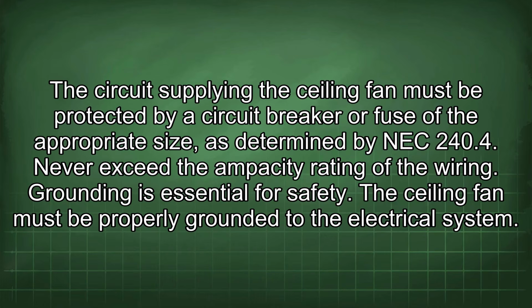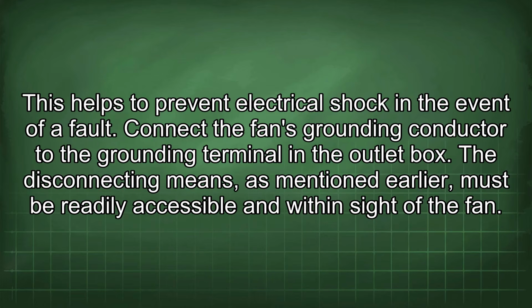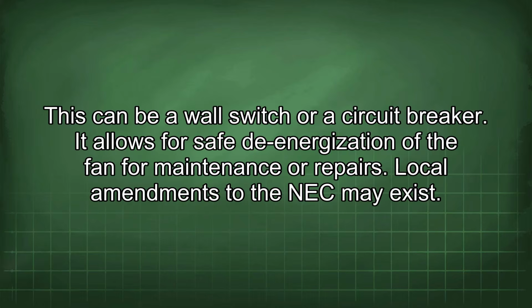Grounding is essential for safety. The ceiling fan must be properly grounded to the electrical system. This helps to prevent electrical shock in the event of a fault. Connect the fan's grounding conductor to the grounding terminal in the outlet box. The disconnecting means, as mentioned earlier, must be readily accessible and within sight of the fan. This can be a wall switch or a circuit breaker. It allows for safe de-energization of the fan for maintenance or repairs.